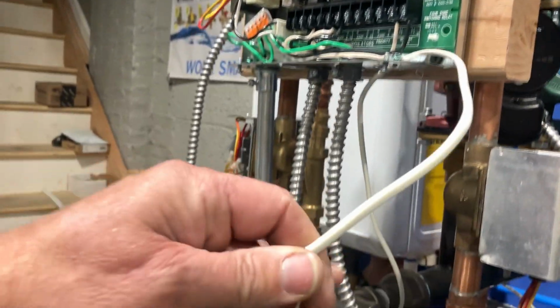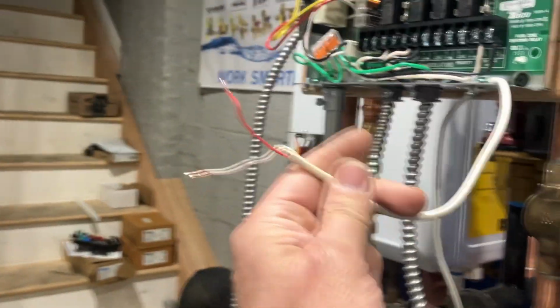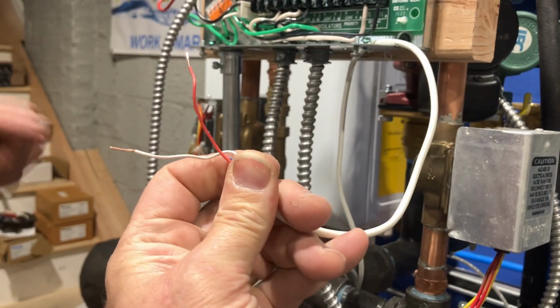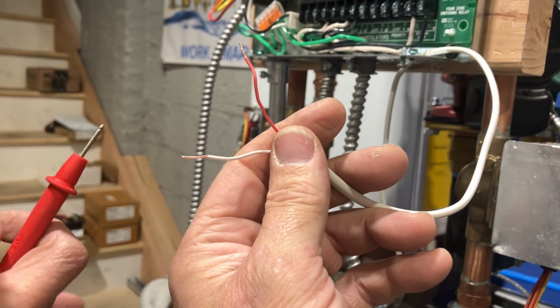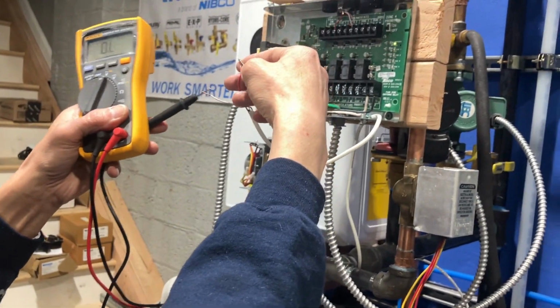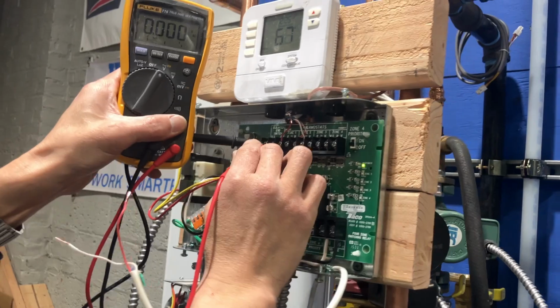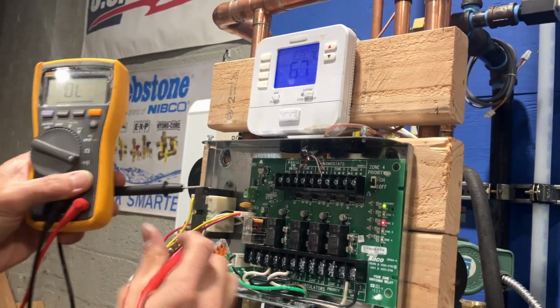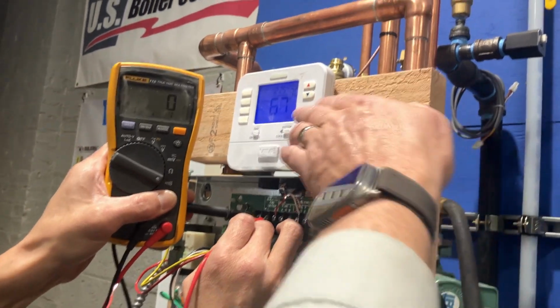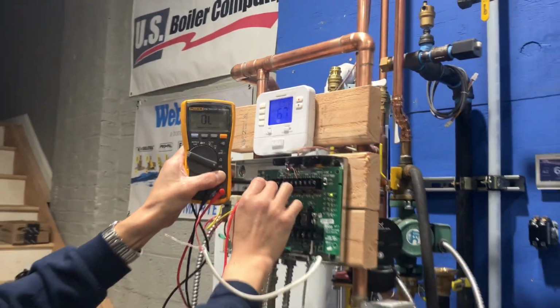Okay, so these wires are eliminated. If you want, you can check for voltage there again. All right, you got 27 volts there. Now check for continuity between them. No continuity. Hold on. Check for continuity. Continuity. Now you have no continuity. Right? Okay. So, we just wired the SR504 4-zone switching relay to the boiler. We wired it to TT and proved that it works.